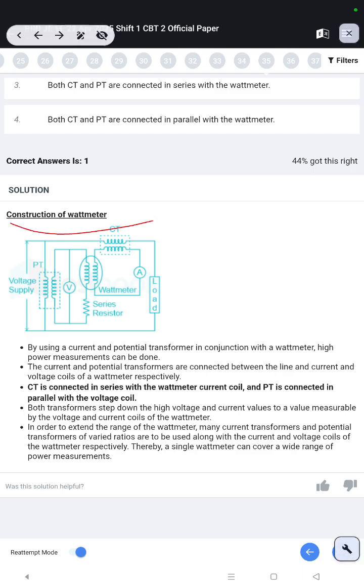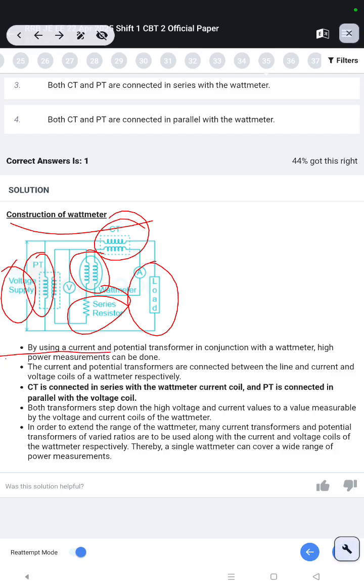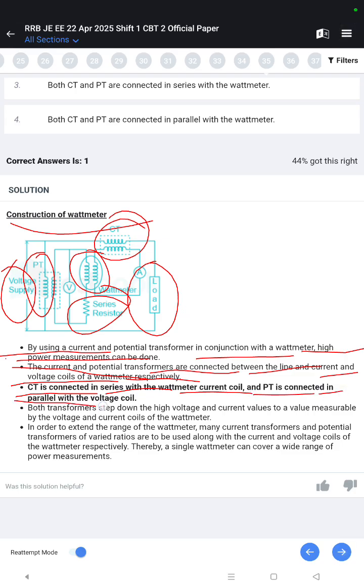Construction of wattmeter: voltage supply, PT, CT, wattmeter, series resistor, load. By using a current and potential transformer in conjunction with a wattmeter, high power measurement can be done. The current and potential transformers are connected between the line and the current and voltage coils of the wattmeter respectively. CT is connected in series with the wattmeter current coil and PT is connected in parallel with the voltage coil. Both transformers step down the high voltage and current values to a value measurable by the voltage and current coil of the wattmeter.